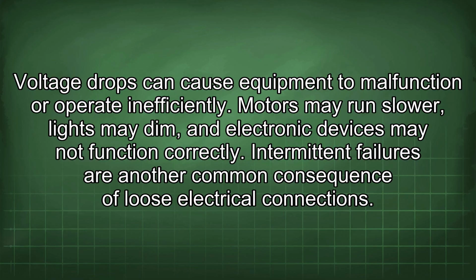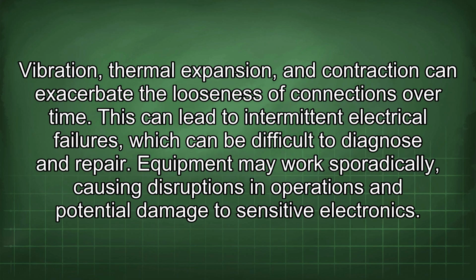Intermittent failures are another common consequence of loose electrical connections. Vibration, thermal expansion, and contraction can exacerbate the looseness of connections over time. This can lead to intermittent electrical failures, which can be difficult to diagnose and repair. Equipment may work sporadically, causing disruptions in operations and potential damage to sensitive electronics.